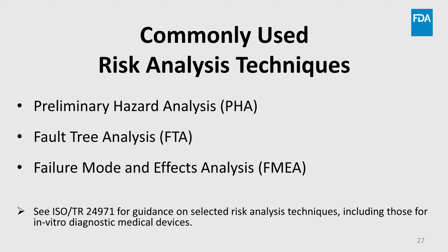Please reference the ISO TR 24971 guidance on selected risk analysis techniques, including those for in vitro diagnostic medical devices. One of the changes to the ISO 14971 2019 standard is the risk analysis appendices were removed and added to the TR 24971 guidance document. It is a great document to look at different risk analysis techniques for medical devices.